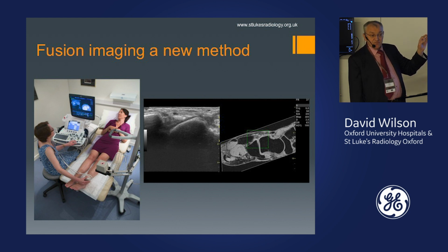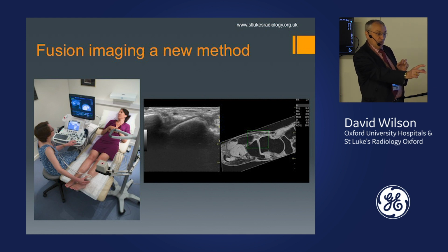The first 20 seconds, perhaps, you spend thinking, is my probe lined up in the same way as the MR or CT? As soon as you're happy it is, and it's usually just a little rotation of the wrist, get the triangle, you think, right, that's correct, you press one button to lock the plane. Now the planes are locked. Whenever I move the ultrasound probe, the ultrasound image will change, obviously, because I'm looking at a different angle, but the MR will change into the same plane.